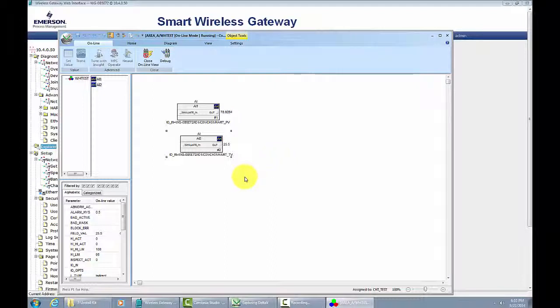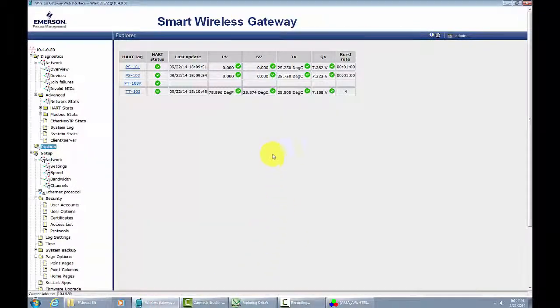And to validate those, we'll move over to the Wireless HART Gateway. And you can see the PV and TV being communicated. When the values are refreshed, they change to a shade of green momentarily and then switch back. So that's an indication that the values are being communicated every 4 seconds, as we configured when we were setting up the device.